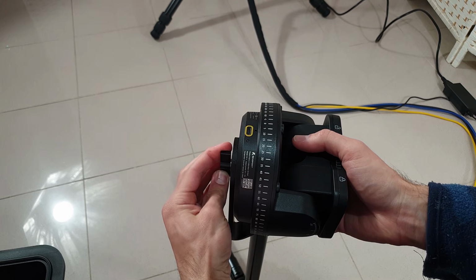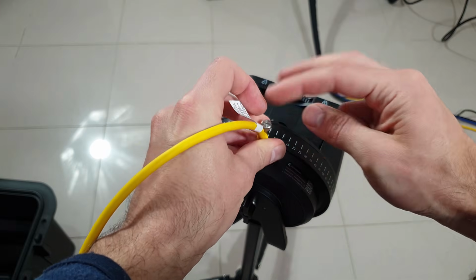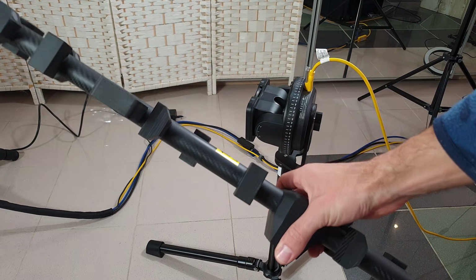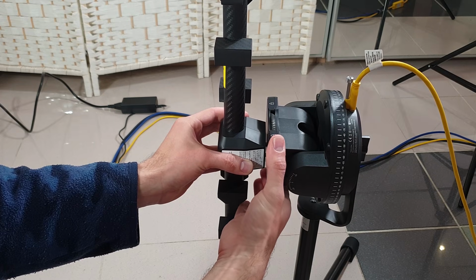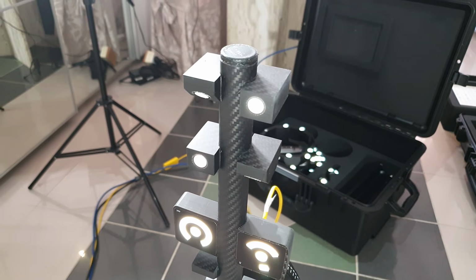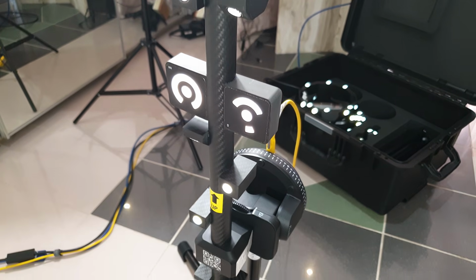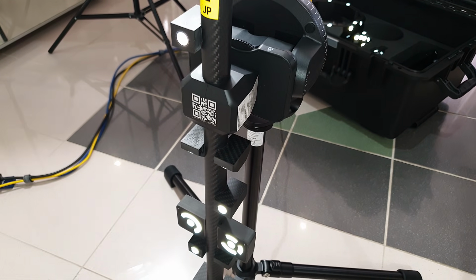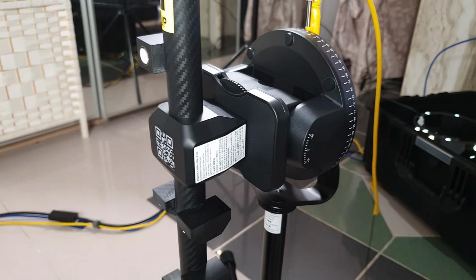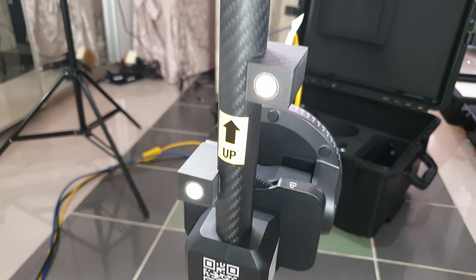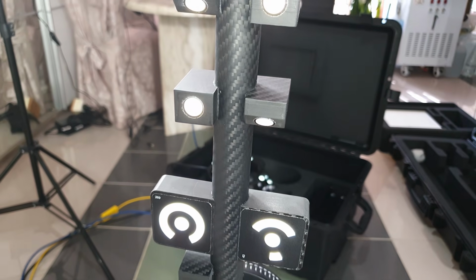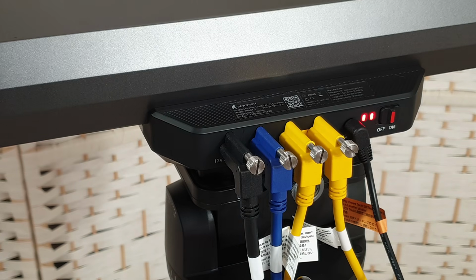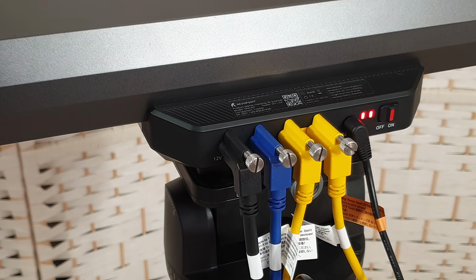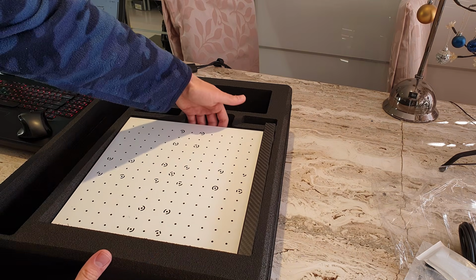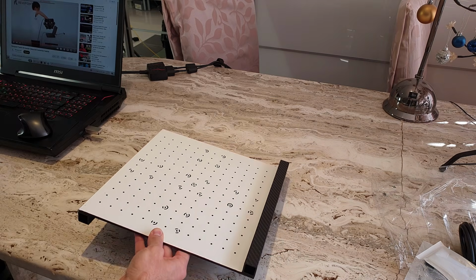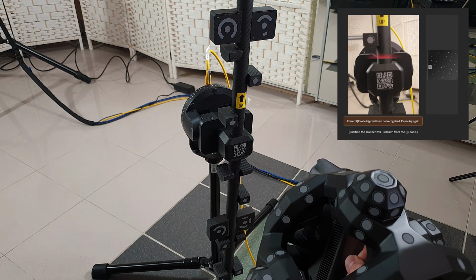The scanner does come calibrated from the factory. However, I wanted to see the calibration process and to demonstrate it in this video. The tripod holding this calibration bar is the same tripod we will be using to calibrate the scanner in the final stage. This scanner uses 2-axis gimbals to automatically calibrate the scanner, removing user error during the calibration stage to give us a better calibration result. However, the calibration process does take around 30 to 40 minutes, so it's not something you want to do every single time you start the scanner.